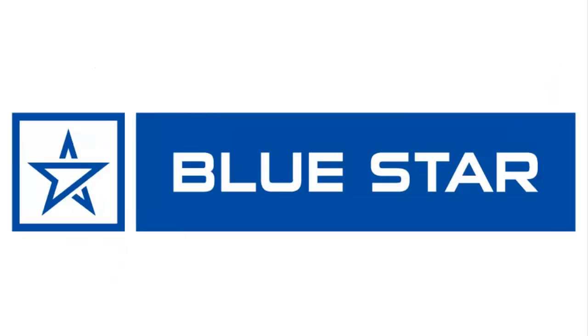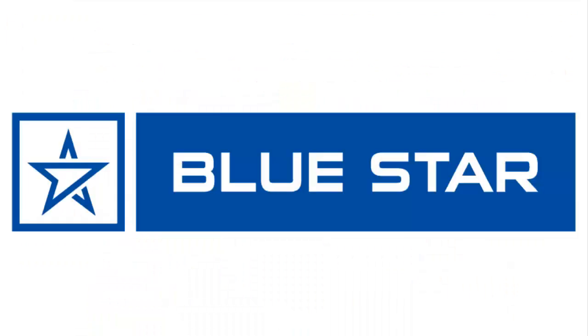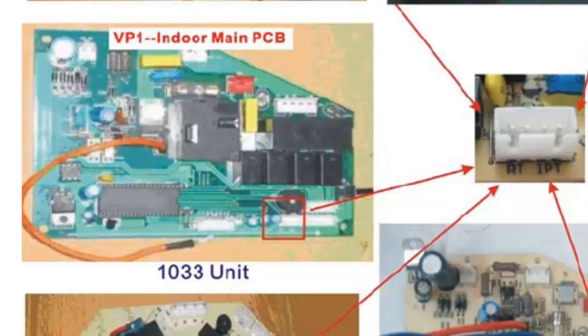7. If you have the unit's manual, compare the measured value with the sensor specification table. If not, replace the sensor. 8. If the error persists, visually inspect the electronic board controlling the sensor for any faults. Consider replacing the involved electronic board if the problem continues.